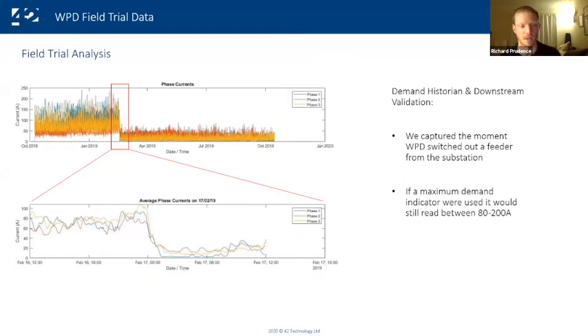The nice realization of this is that if we were to rely on what the maximum demand indicator in the substation was stating, it would state a maximum of somewhere between 80 to 200 amps. The new reading, based on what we were looking at, is actually nearer 40. So it just goes to show that we designed something and it has fulfilled its purpose quite well.